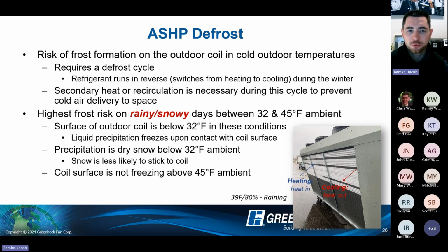Couple other points, the highest frost risk on rainy and snowy days is between 32 and 45 degrees ambient. And this is exactly why we're seeing frost conditions on this 39-degree day. When you're below 32, liquid precipitation freezes upon contact with the coil surface, right? So it's not going to necessarily freeze the coil. Precipitation is dry snow below 32 degrees, so the snow is less likely to stick on the coil if you're overall below that 32 degrees. And then above 45, you're not necessarily worried about it because the coil surface is not freezing. So that 32 to 45 degrees is that sweet spot where that surface is below freezing, but then you have moisture that's going to freeze on that coil.